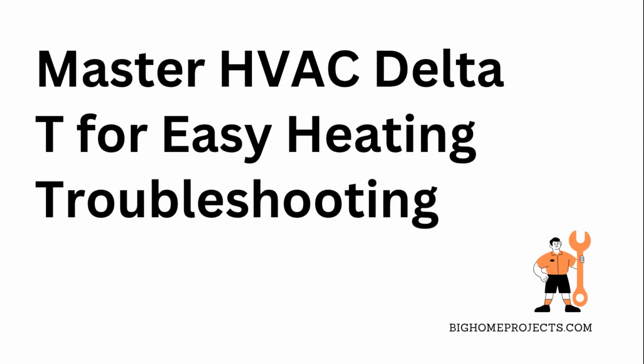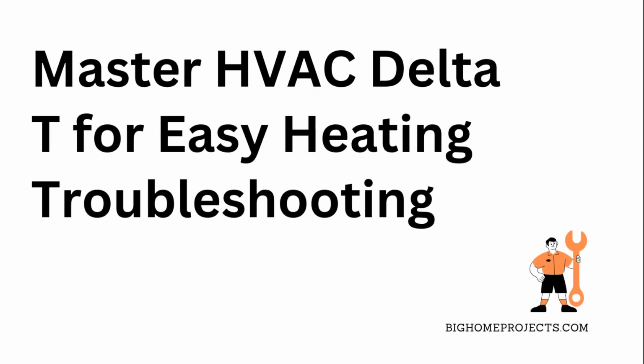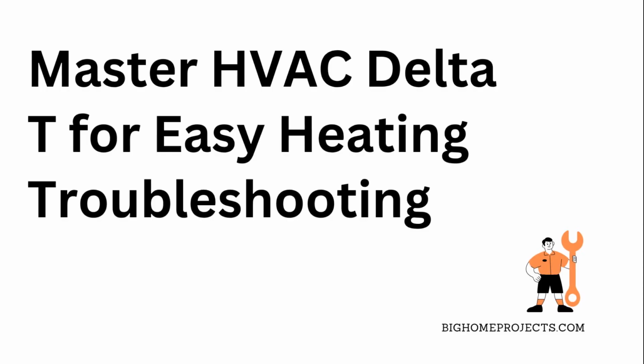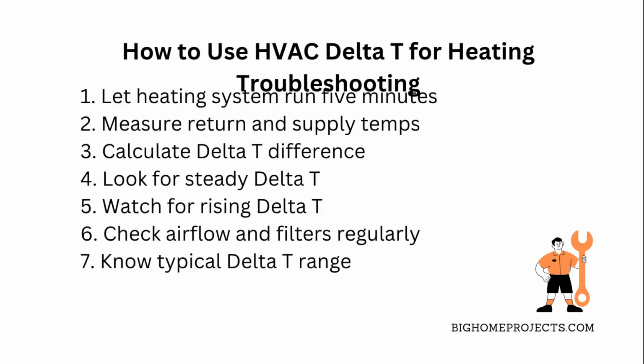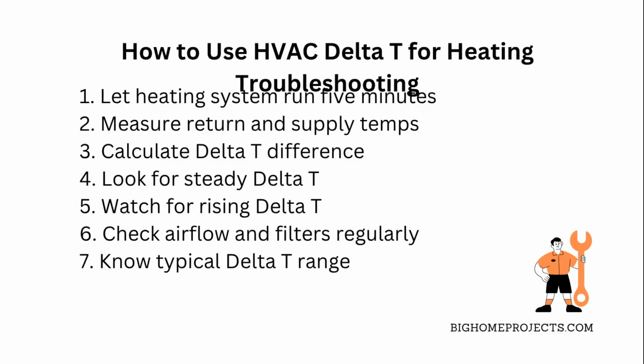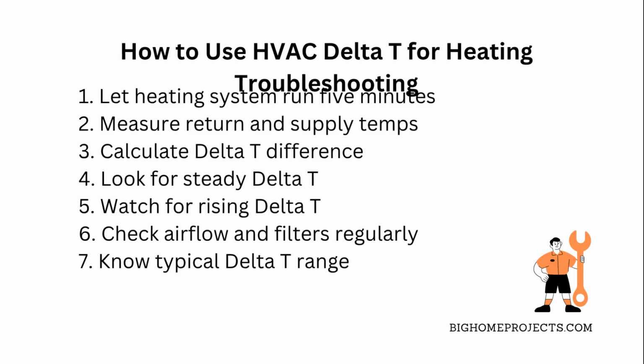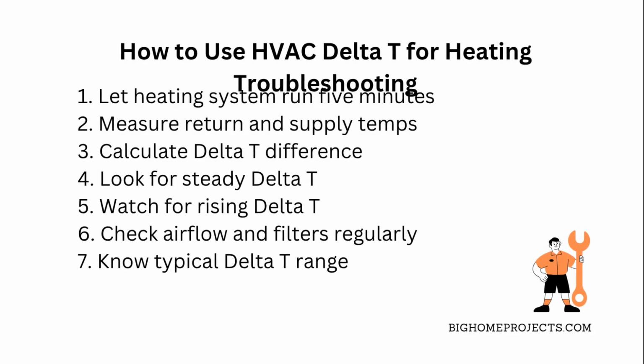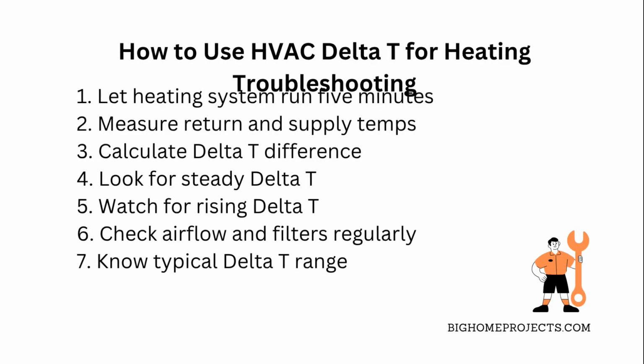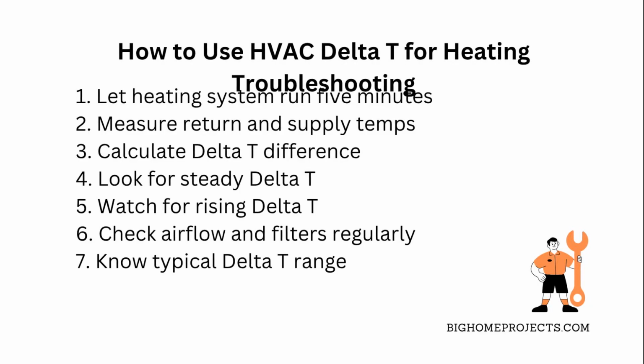If you want to troubleshoot your heating system like a pro, understanding HVAC Delta T is the game changer you've got to know. So, Delta T is basically the temperature difference between your supply air and your return air in heating mode. To use it right, start by turning your heating system on and let it run for about 5 minutes so everything stabilizes. Then grab your thermometer or temperature sensor and measure the return air temperature coming back to the unit and the supply air temperature going out.